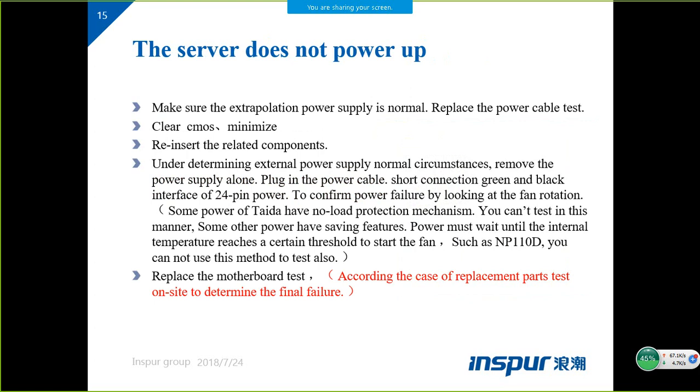And the next phenomenon of typical issue is the server doesn't power up. No power on means no indicator. There's no light from the indicator. So you need to make sure the PDU works normally.